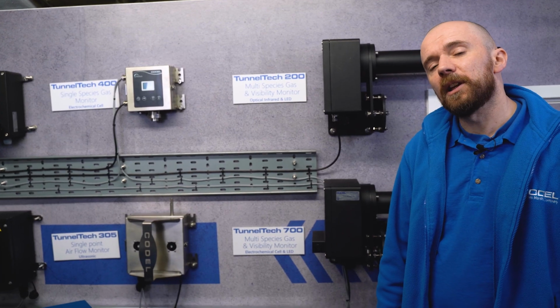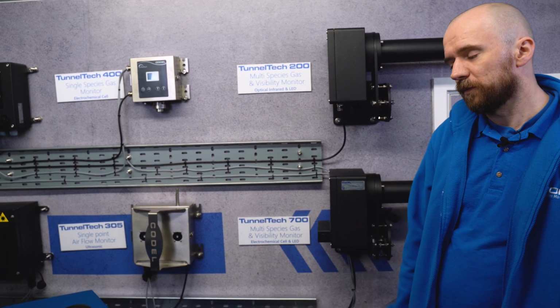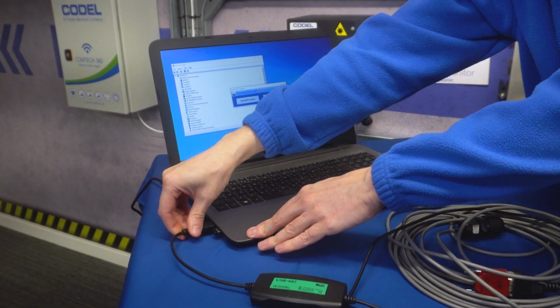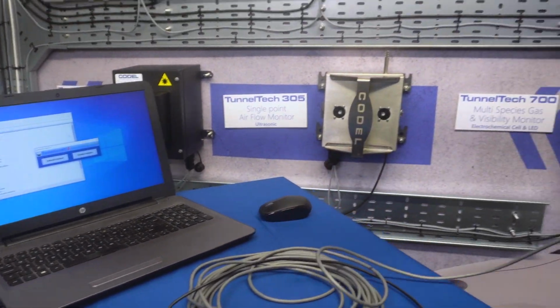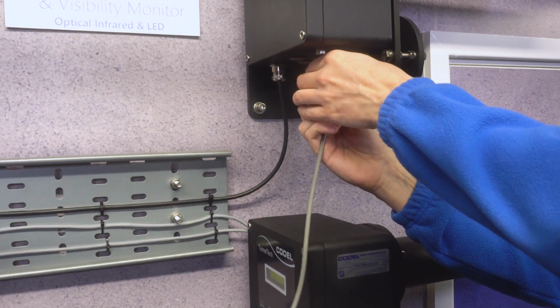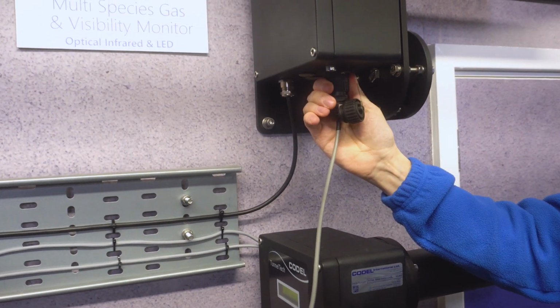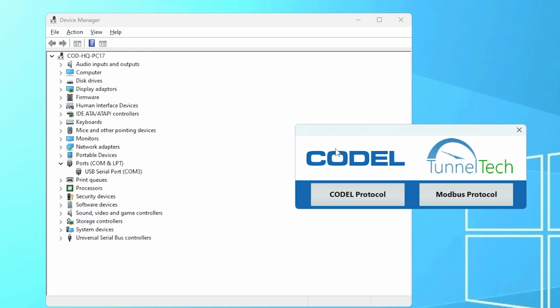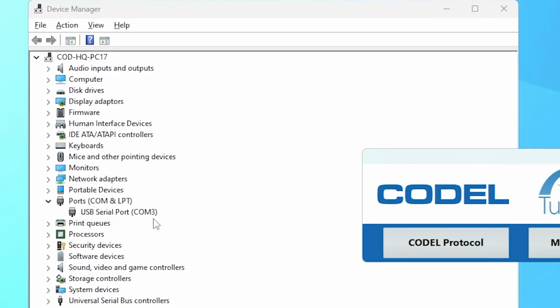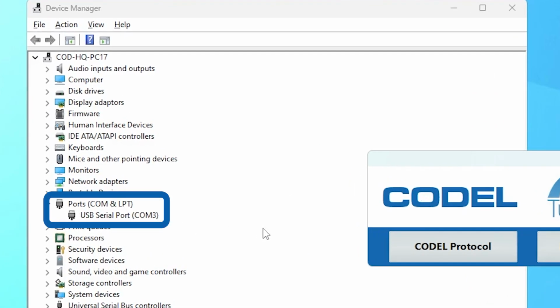For this, you're going to need a PC connection, the TunnelTech software, which can be downloaded from our website, links are in description, a comms cable, and an understanding of which COM port has been assigned to that comms cable. Now we're going to connect the TT200 to the PC. With the comms cable connected, in Device Manager you should see a COM port assigned to the USB converter, in our case COM port 3.